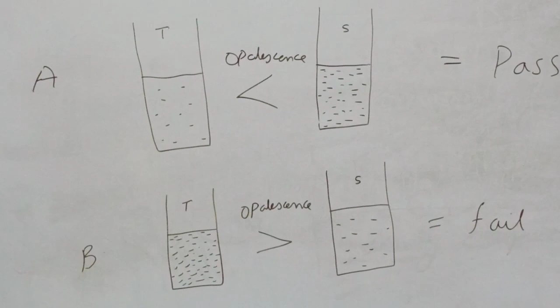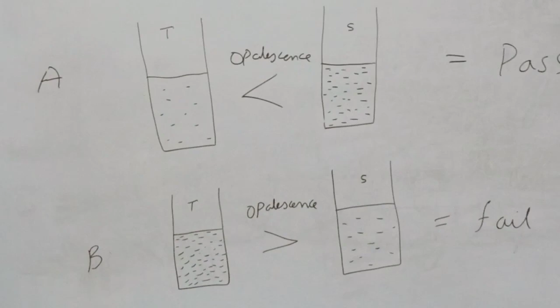So while we are comparing situation B, we can see here that the standard that is marked as S has a lesser dotted line compared to the test under situation B, and the test has a greater dotted line. So we can analyze here that the test has a greater opalescence or turbidity compared to the standard under situation B. This means the test contains the greater amount of sulfate as an impurity compared to the standard.